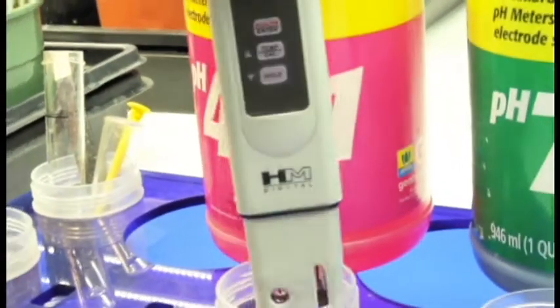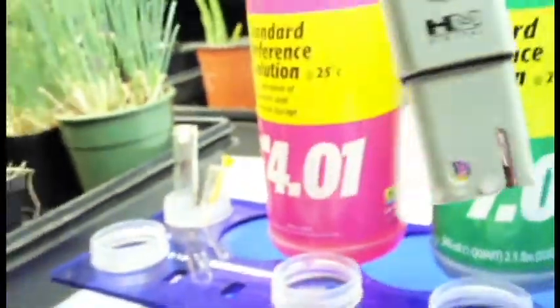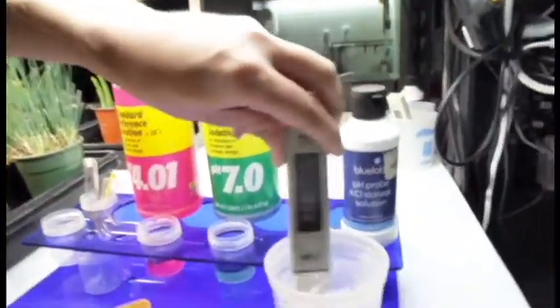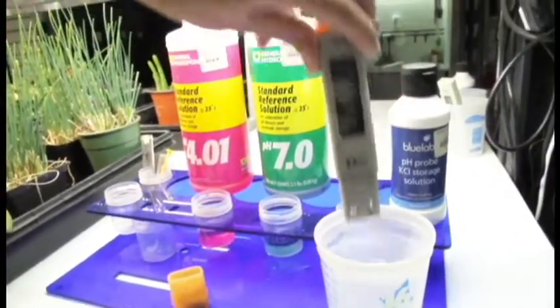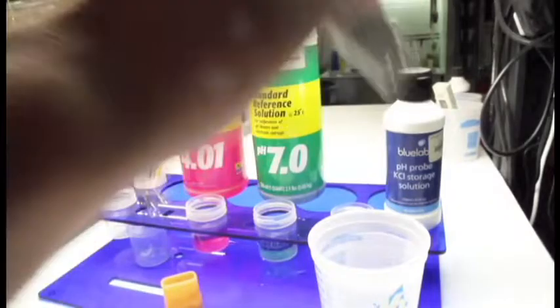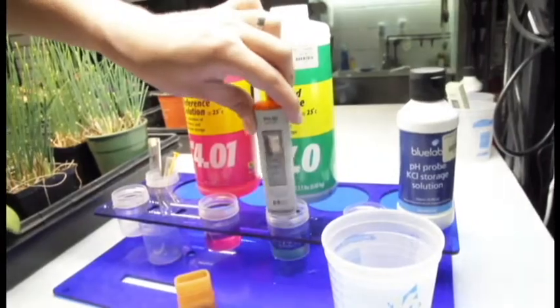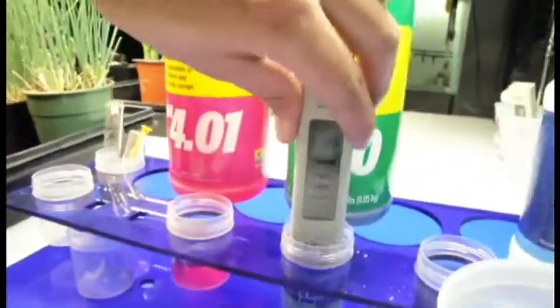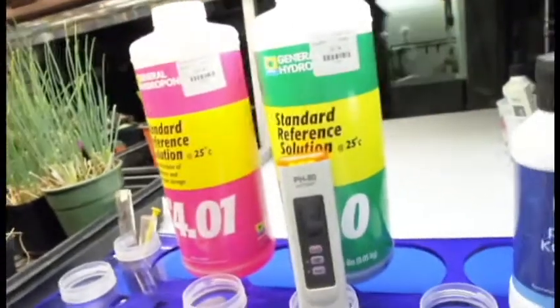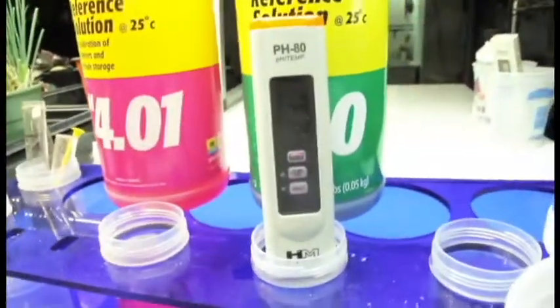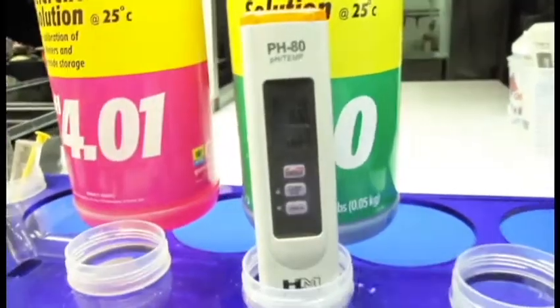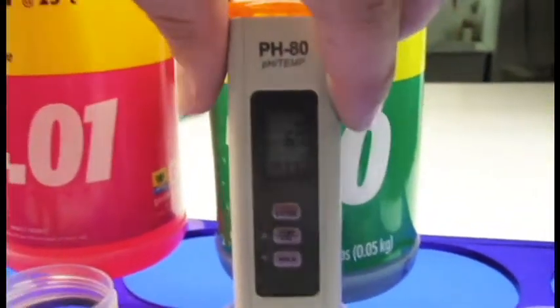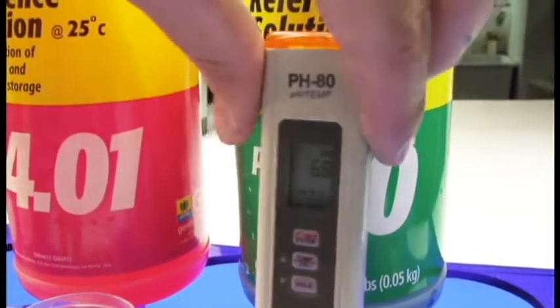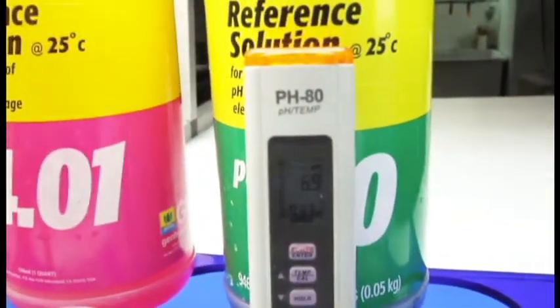I'm going to remove it from the solution, being careful not to let anything drop into my 7.0 that is sitting next to it. I'm going to bring it over to my fresh water and rinse off that 4.0. I'm going to give it another good little shake to get all those little water droplets off. And now I'm going to stick it over here in my 7.0. Once again, I'm going to let it stabilize after I give it a little tiny stir. We're going to let it do its thing. As it's moving, I'm going to give it another little stir. It helps quicken the process and dilute that tap water down.